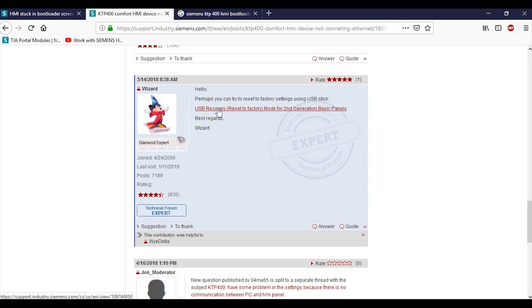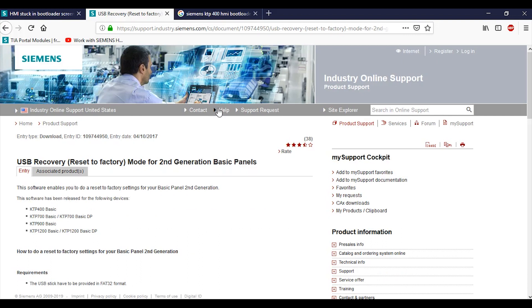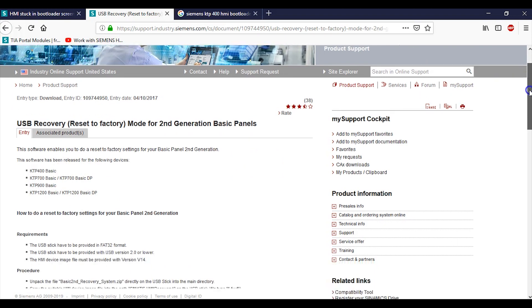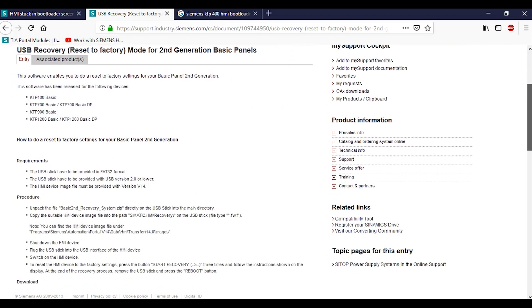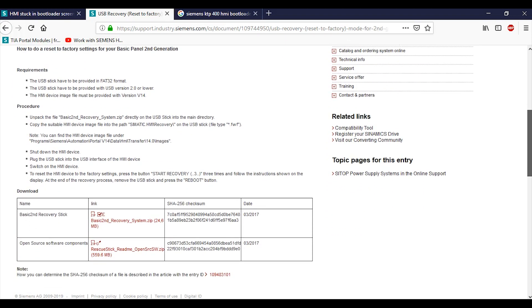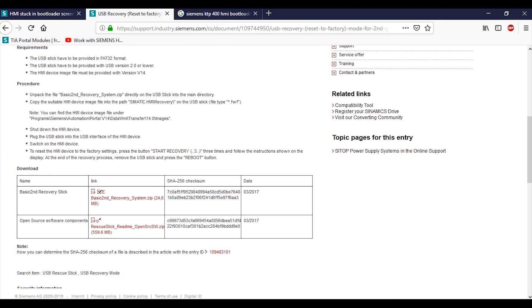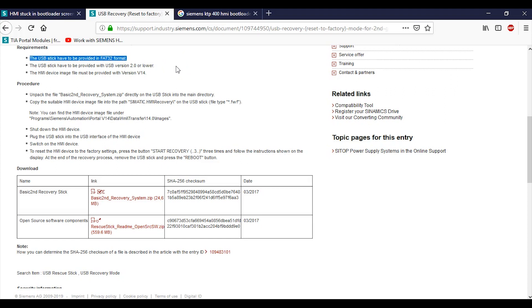So you click on this guy right here: USB recovery reset to factory mode for second generation basic panels. I'll put all of this as links below. Software has been released for these guys. If we scroll down, how do you reset to factory settings for your basic panel? Requirements: you need a USB stick to be provided in FAT32 format. The USB stick has to be provided with USB version 2.0 or lower. The HMI device image file must be provided with version 14 or higher.